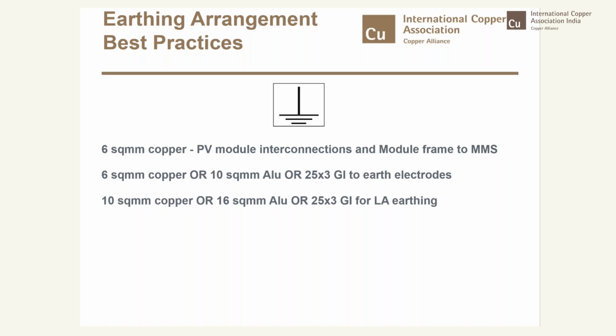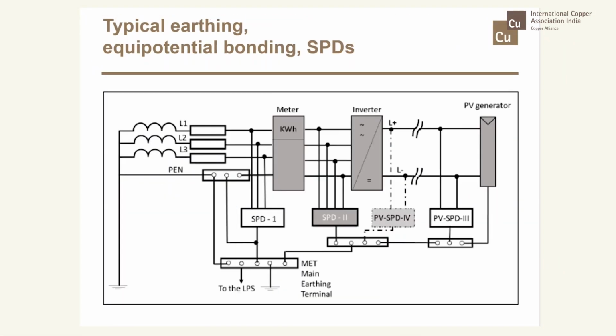In fact, you can have 6 square mm or 10 square mm aluminium or 25x3 GI to the earth electrodes from the MMS also. And for lightning arrestor earthing, we need to have 10 square mm copper or 16 square mm aluminium or 25x3 GI flat for lightning earthing. This is strictly restricted to domestic rooftop systems. You can see the earthing single line diagram, where between the PV generator and the inverter you need to have surge protection devices, and different categories are also shown.